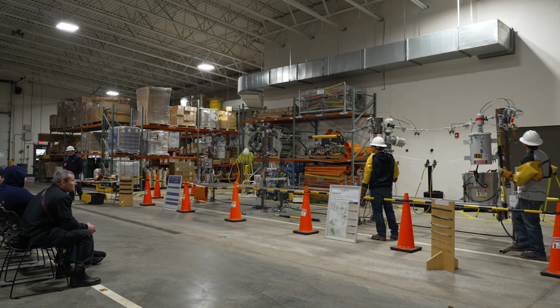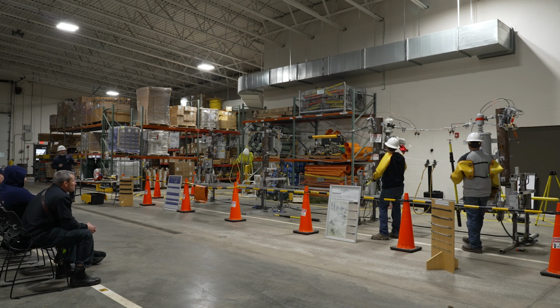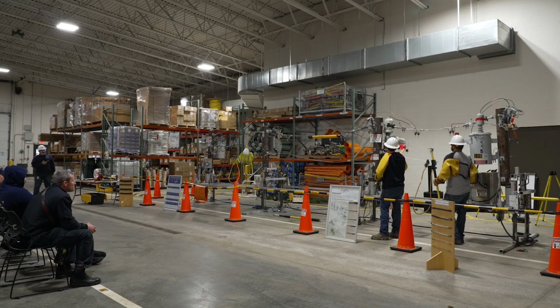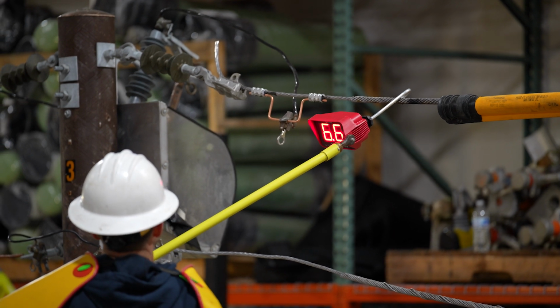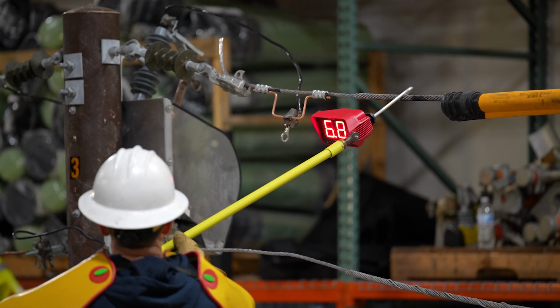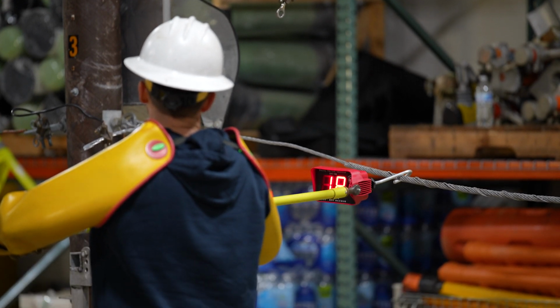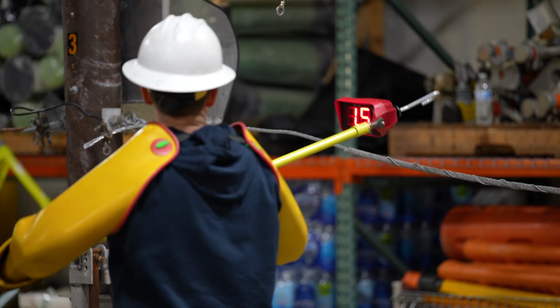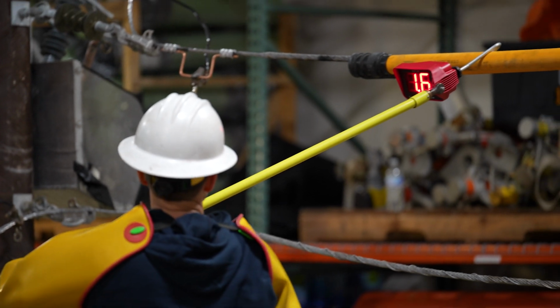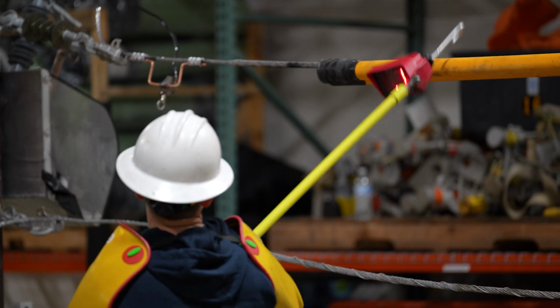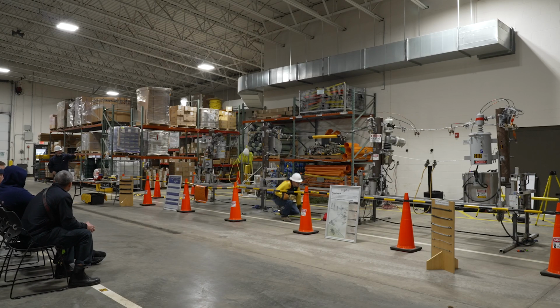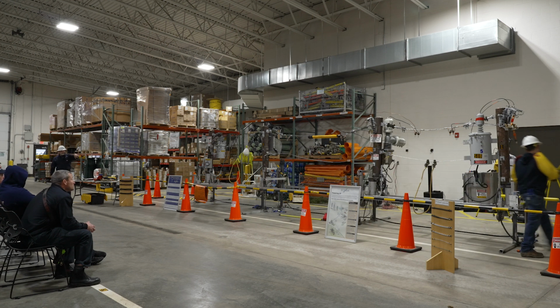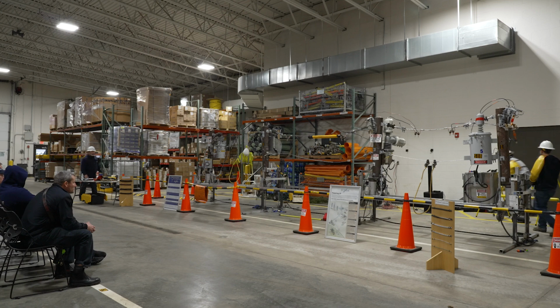Here we're using a DVI, a digital voltage indicator, to check voltage on our circuit. We're running 6,700 volts. On our neutral, we have 1,700 to 1,800 volts coming back to the source. So a neutral will kill you as fast as a phase, because people start taking half steps when dealing with neutrals, and it's just as dangerous.